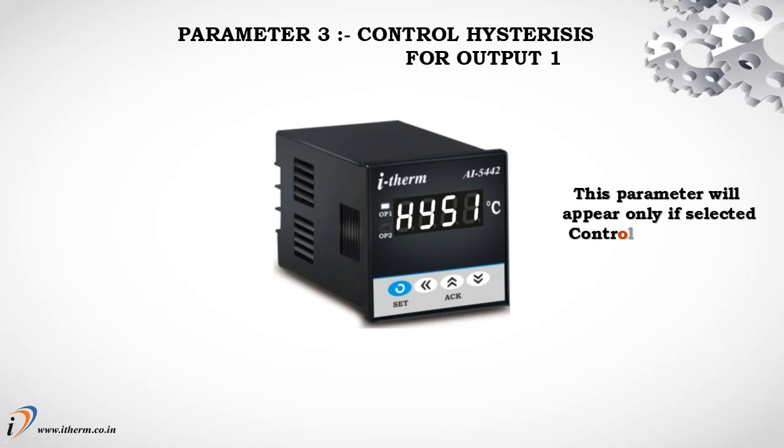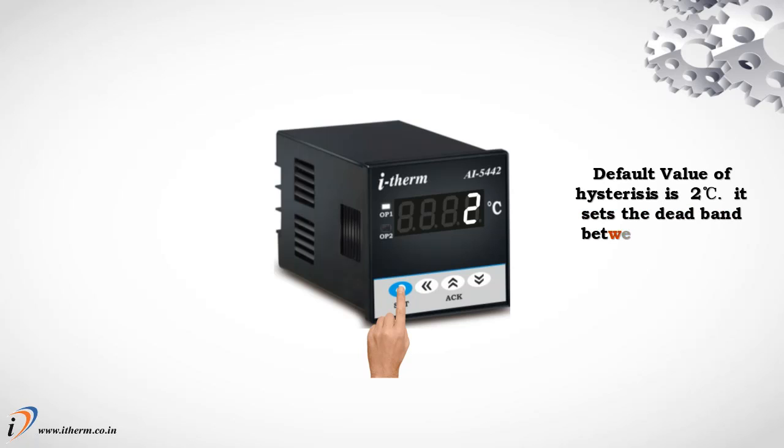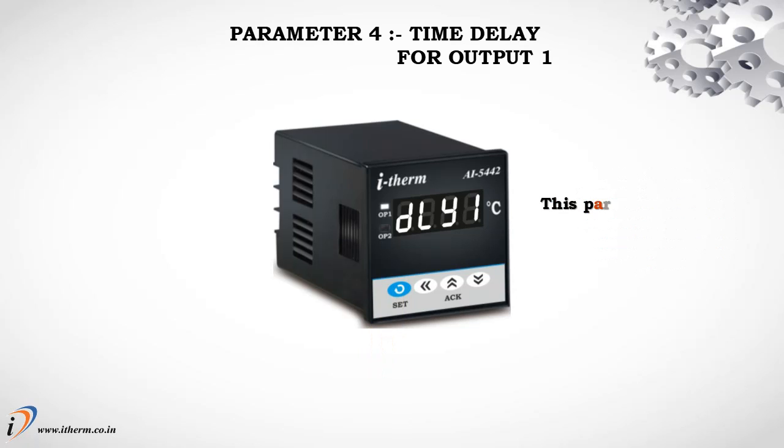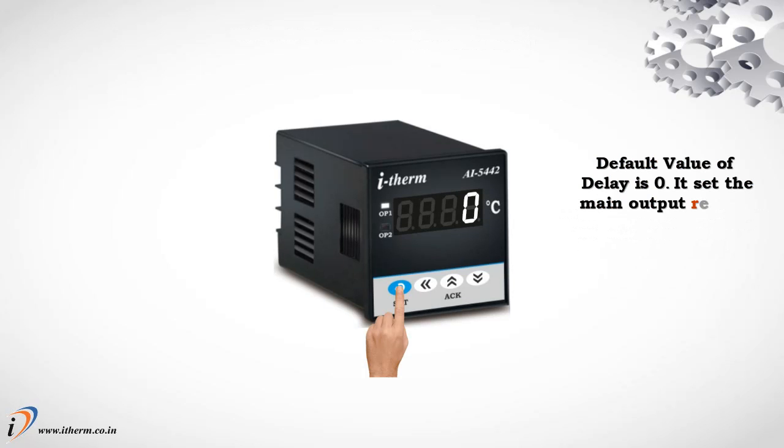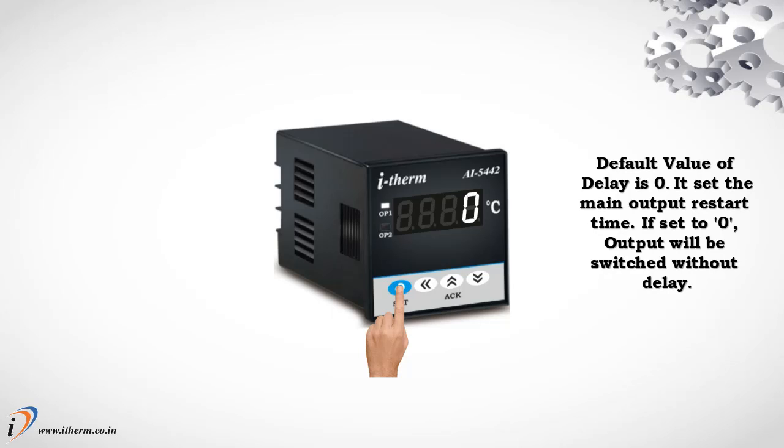Parameter 3. Control hysteresis for output 1. This parameter will appear only if selected control action is on/off. Default value of hysteresis is 2 degrees centigrade. It sets the dead band between on and off switching of the output. Parameter 4. Time delay for output 1. This parameter will appear only if selected control action is on/off. Default value of delay is 0. It sets the main output restart time. If set to 0, output will be switched without delay.